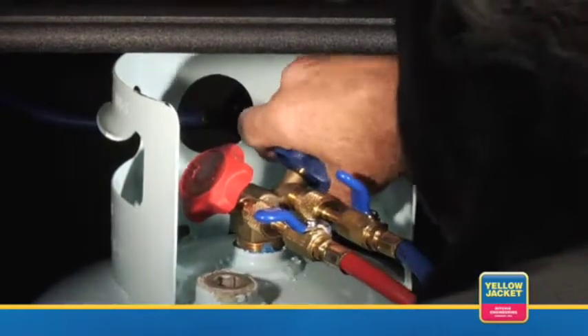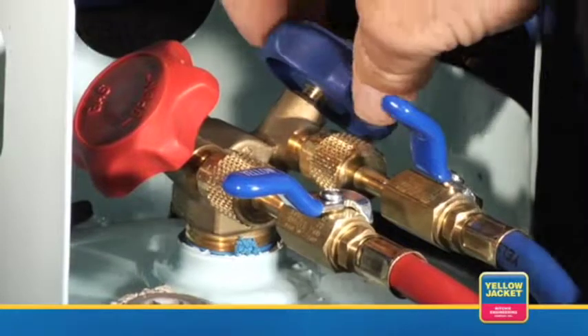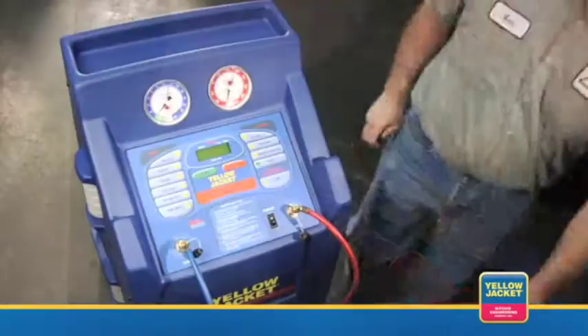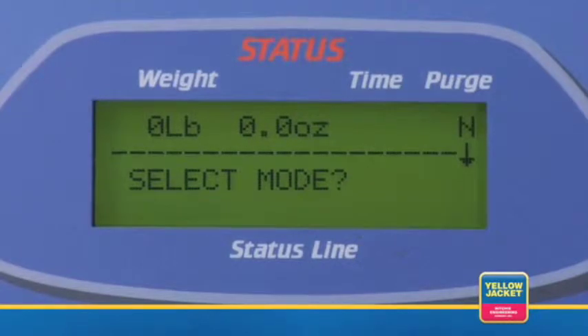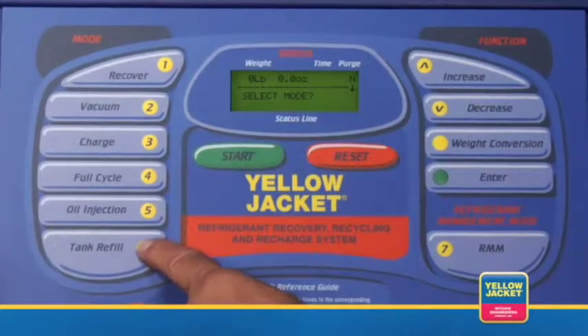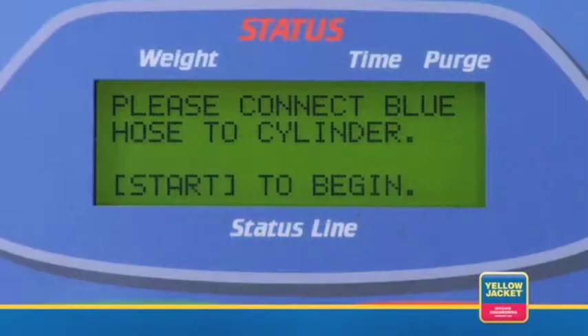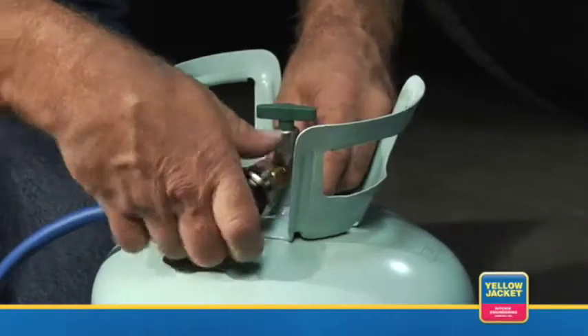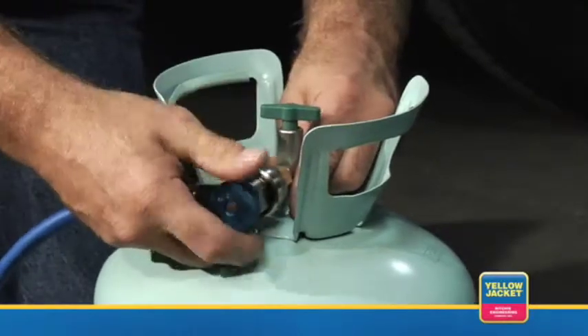Open the valves on the tank located in the lower rear of the unit. Power up the machine, and when the display reads Select Mode, press the tank refill button. You will then be prompted to connect the blue hose to the R134A cylinder. Do not open the valve on the R134A cylinder at this time. Connect the blue hose with the low side coupler to the tank refill adapter.